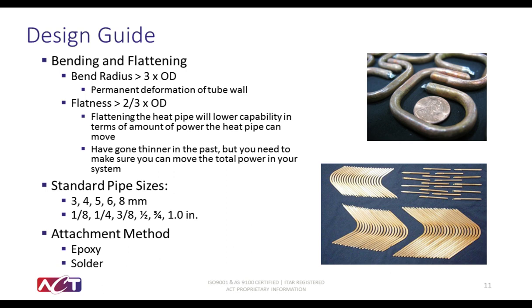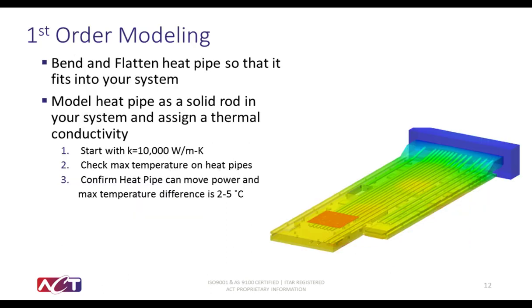So now that you've designed the heat pipe mechanically and understood that it can carry the amount of power you're looking for, you're going to integrate that heat pipe into your model and do some modeling to find out how it performs. To do this, ACT has some first-order modeling guidelines that you can follow. Take that heat pipe, embed it into your mechanical design as a solid element, and apply to it a starting conductivity of about 10,000 watt per meter K. For reference, aluminum is about 200 and copper is about 400. Run your simulation and check the maximum temperatures across that heat pipe element.